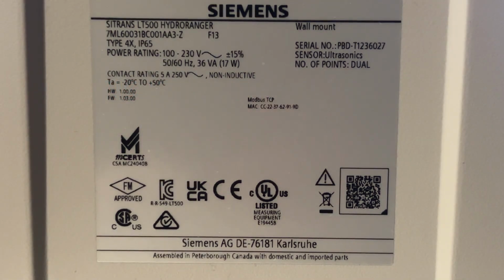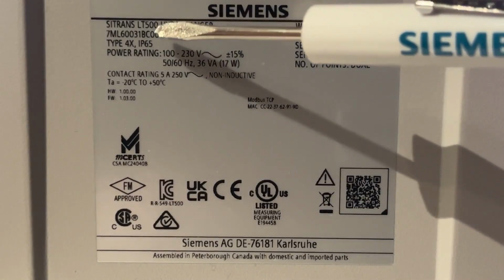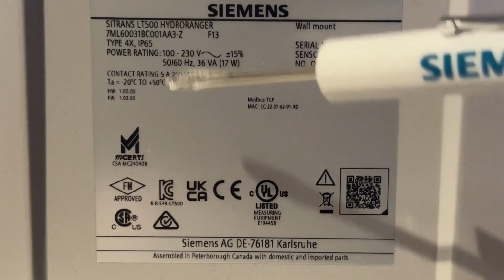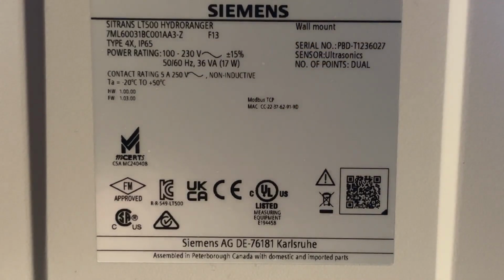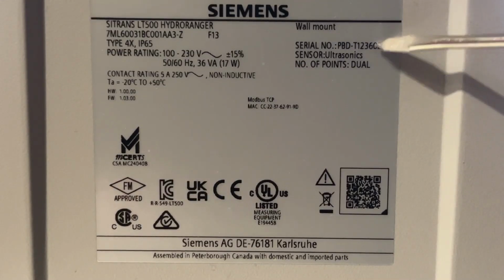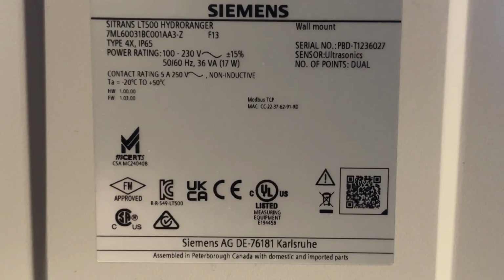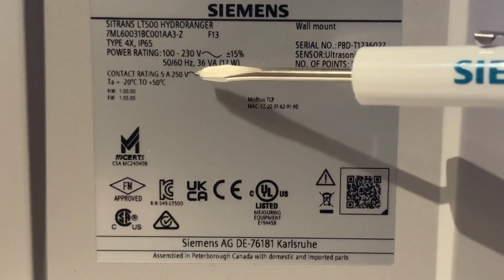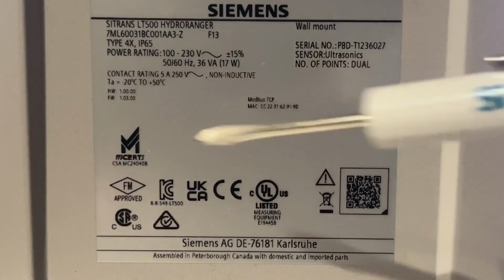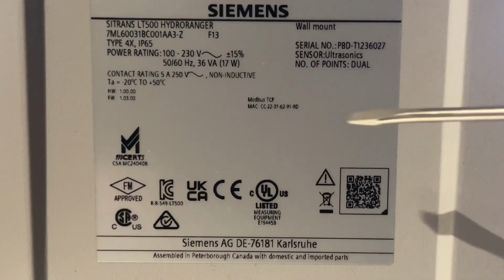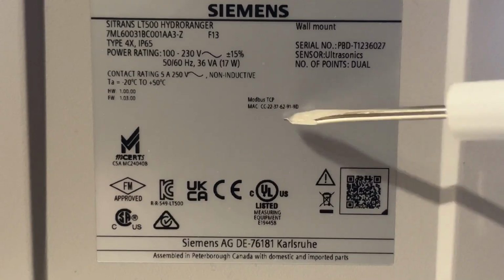When you first receive your LT500, you'll notice some valuable information on the product nameplate. First, the part number with any order codes are listed, your enclosure and power ratings, whether it's AC or DC, what type of mounting it is, wall mount, panel mount, remote panel mount, the serial number, the type of sensor input, so whether it's a milliamp analog or ultrasonics, the number of points, single or dual point, information around the temperature spec, the relay outputs, the hardware and firmware number, and, if applicable, a communications card identifier and the MAC address.